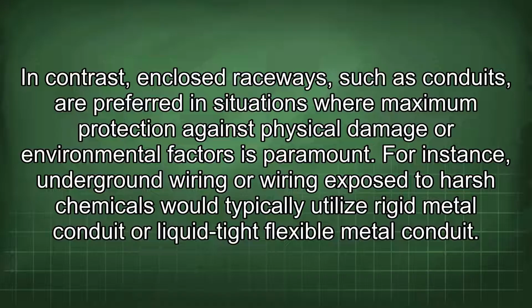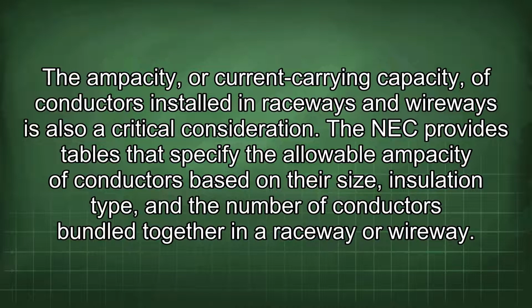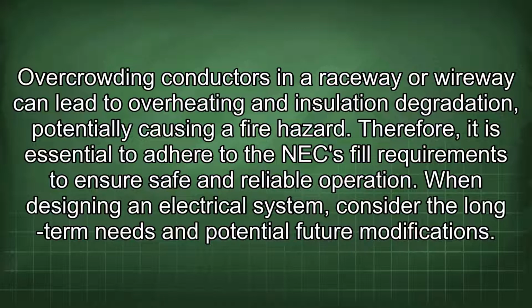flexible metal conduit. The ampacity, or current carrying capacity, of conductors installed in raceways and wireways is also a critical consideration. The NEC provides tables that specify the allowable ampacity of conductors based on their size, insulation type, and the number of conductors bundled together in a raceway or wireway. Overcrowding conductors in a raceway or wireway can lead to overheating and insulation degradation, potentially causing a fire hazard. Therefore, it is essential to adhere to the NEC fill requirements to ensure safe and reliable operation.